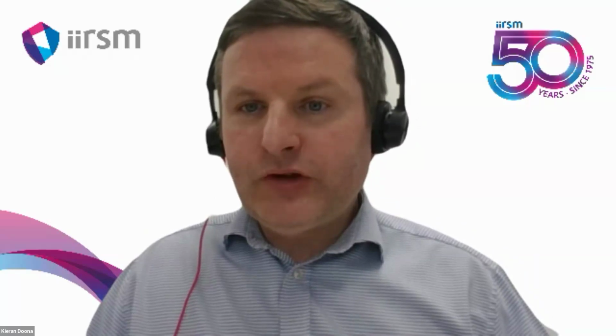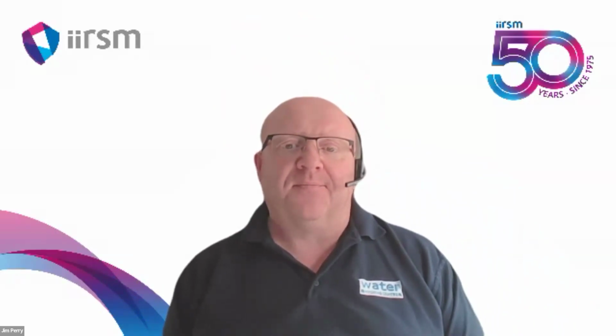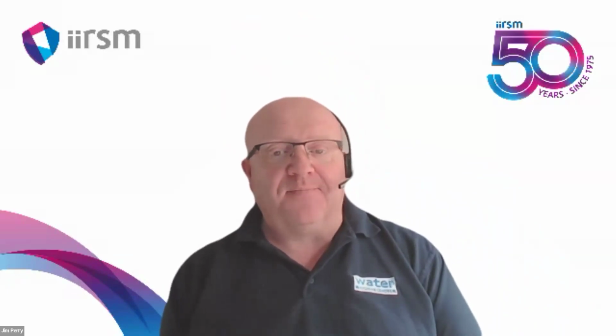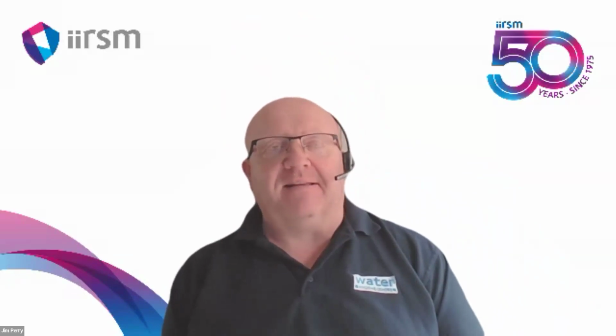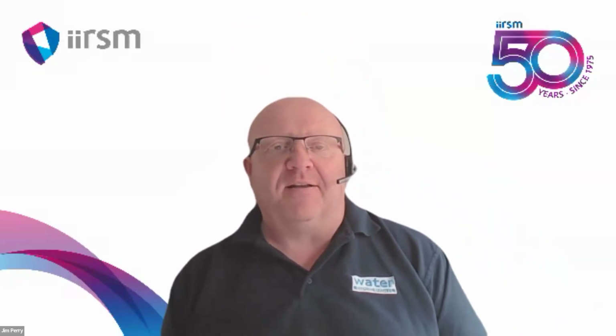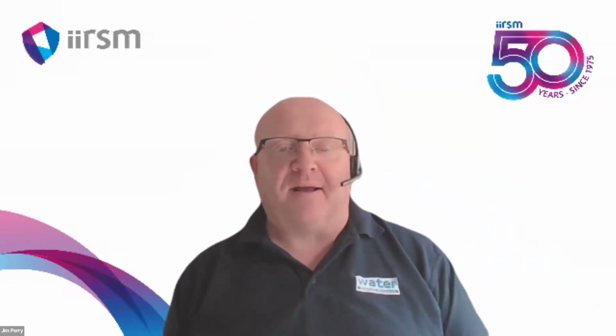Charles asks, is there any new technology or equipment on the market that is helping to control these issues? There is. You can have secondary dosing systems on your water systems, things like chlorine dioxide, chlorine, silver, copper dosing systems. They help with the control method. But again, if you're not flushing your outlets, the secondary control method's not going to get there. So it's horses for courses. Realistically, if we can keep the outlets clean, keep the water flowing, keep the water the right temperature, keep the water clean, that's the best mechanism.